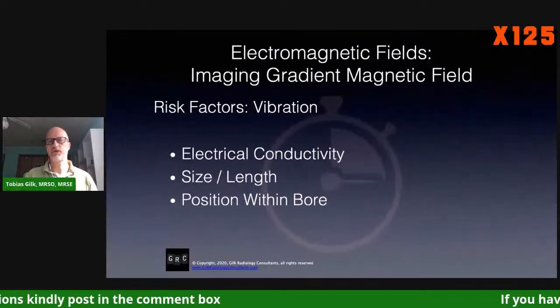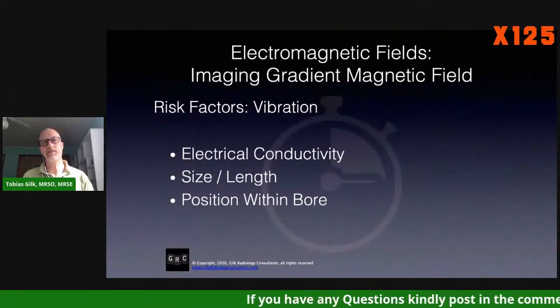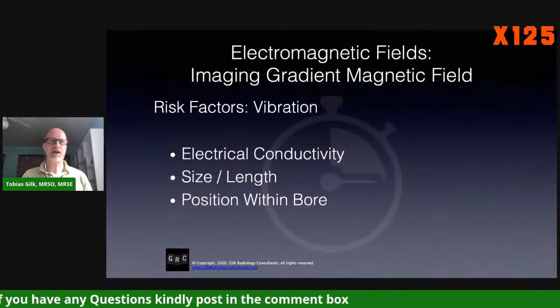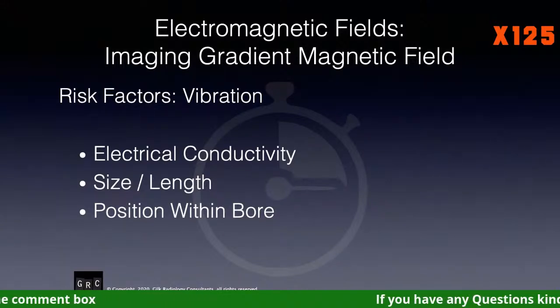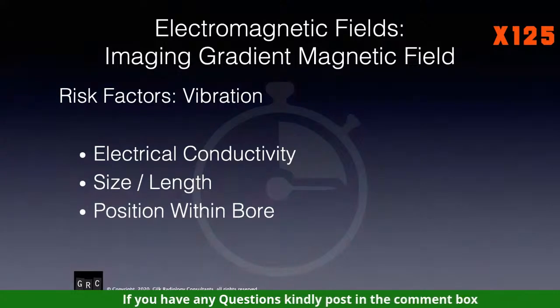The other risk factor is vibration. Vibration is a product of the electrical conductivity of the object or material that may be vibrated, and its size or length. The larger an object is, particularly one capable of supporting a circuit of current, the greater the potential risk. So a large circular object would be amongst the worst. And then there's the position within the bore, because just like the neurostimulatory effects, the vibratory effects are a product of the magnitude of the time-varying gradient energies, which vary depending on the location. So let's talk about what those locations are and how they vary.